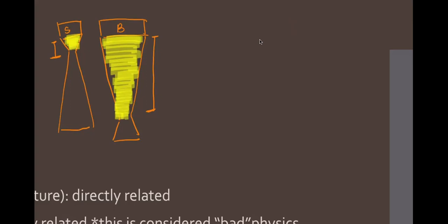If my PZT size, my aperture, increases, I put size, maybe I should have put A, right? So if my aperture increases, like it gets bigger, like a big aperture, my near zone length also increases. Increase just means bigger. If arrows confuse you, then literally write, if aperture increases, my near zone length increases.